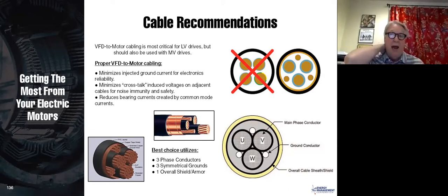The second thing you do is you use 3-phase symmetrical grounds. Most cable have a ground conductor, but if you use these VFD rated cables, they actually have 3 ground conductors, at least most of them. And so here's a ground, here's a ground, here's a ground. Why? Again, you want to keep the capacitance between each of those phases and ground the same. So you're going to have 3 symmetrical grounds. And then finally, you're going to have an overall shield, which tries to keep the noise inside and keep the capacitive currents inside. So these are great cables.